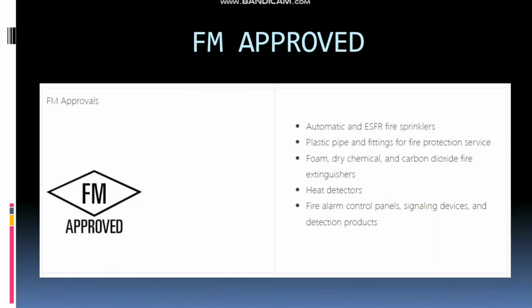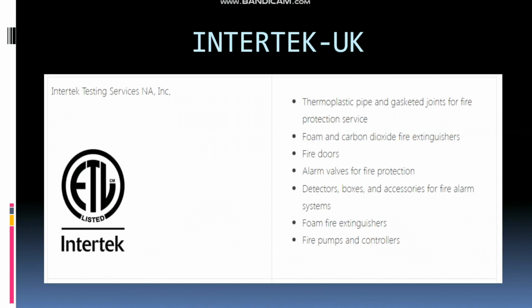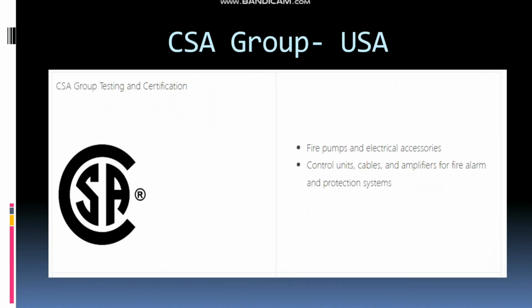So similar to UL listed, with FM approved there are lots of components they are approving, like automatic ESFR fire sprinklers, plastic pipe, CPVC pipes and fittings, foam, dry chemical extinguishers, detectors, signaling devices and lots of things like this. So mostly you see FM and UL, and here is another one, Intertek UK. This is approving thermoplastic pipe, gasket joints, alarm valves, fire pumps, controllers, foam fire extinguishers. So this is also famous in Europe and the Middle East. Another one is CSA Group testing and certification. Mostly they are for fire pumps and electrical accessories. Also you can see control units, cable and amplifiers for fire alarm and protection systems. So this is again famous in the USA, not in the Middle East and other regions.